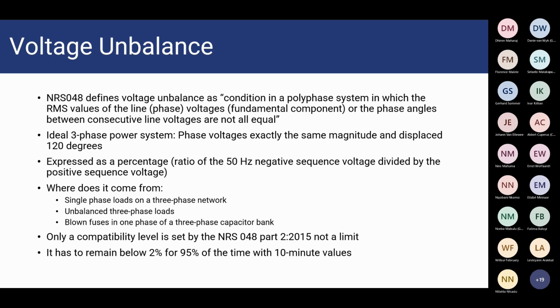What causes voltage unbalance? Large single-phase loads on a three-phase network will lead to voltage unbalance. Unbalanced three-phase loads, or for example a blown fuse in one phase of a three-phase capacitor bank, can also lead to voltage unbalance. All right, for the assessment of voltage unbalance, a compatibility level is set and defined in the NRS 048 Part 2. It's not a limit, it's a compatibility level, and the compatibility level is 2%. So your 10-minute aggregate voltage unbalance value, expressed as a percentage, needs to be below 2% for 95% of the time. That is the assessment criterion.